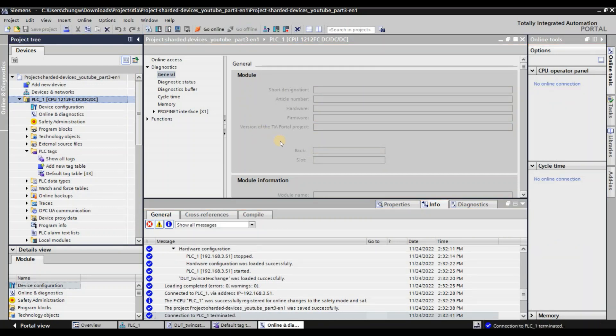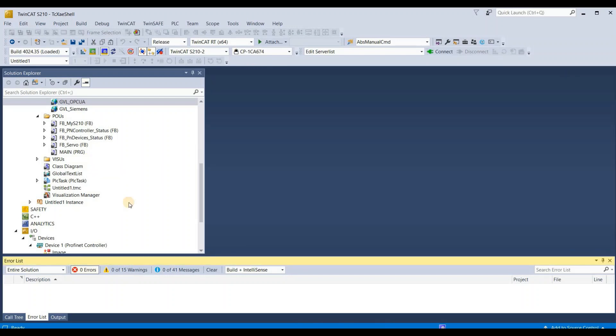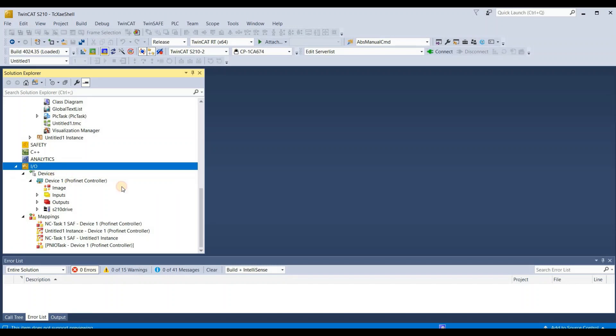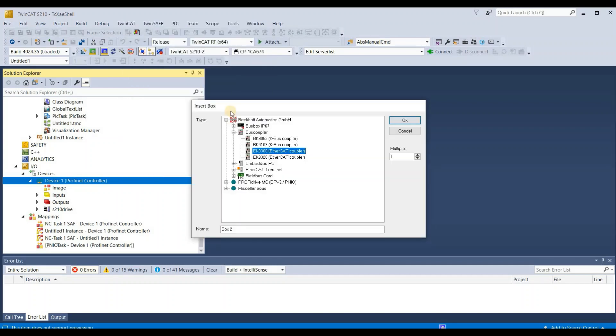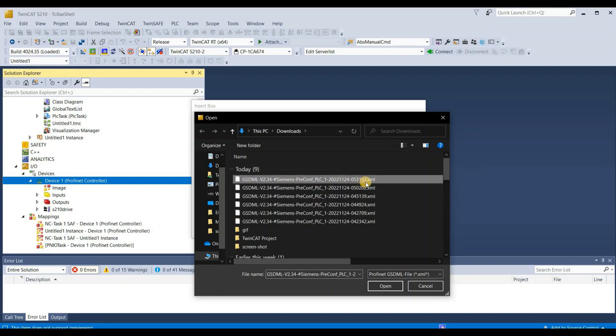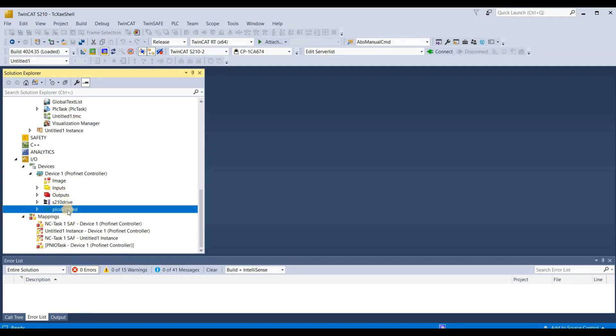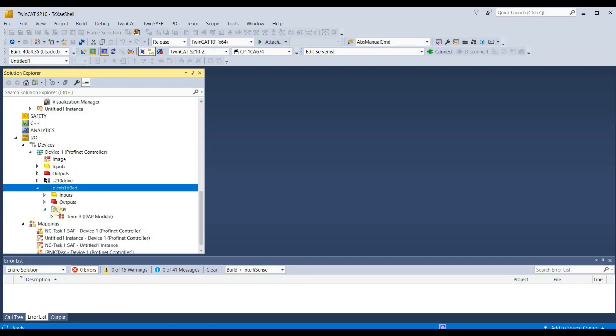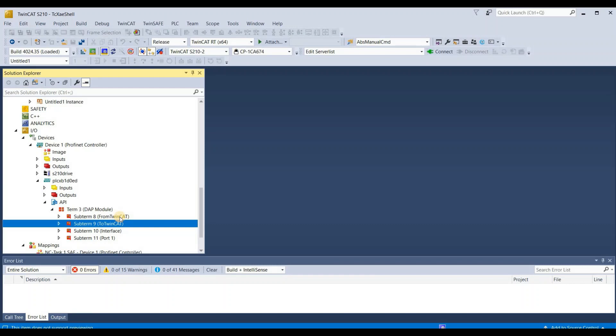Our next step is to go to the TwinCAT side to configure the Profinet network. Open the TwinCAT project from the last step. Go to IO and Devices. This is our Profinet IO controller. Right-click, add new items, choose Profinet IO device, and click it. Then choose the GSDML file that we exported in the last step.